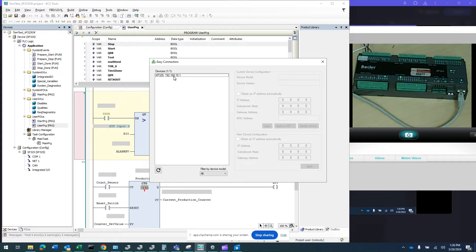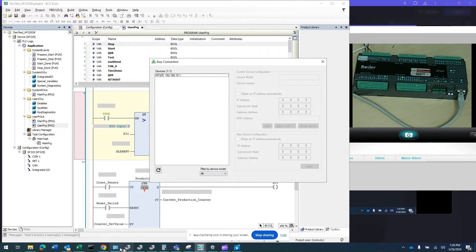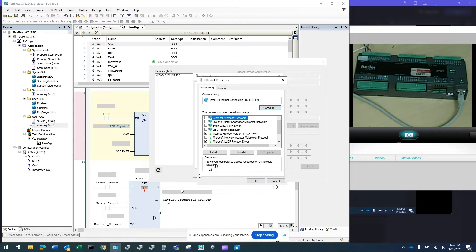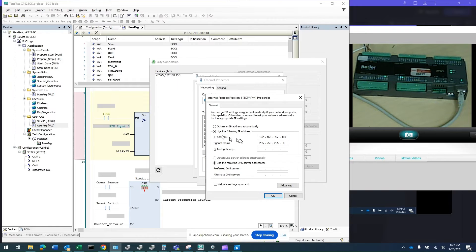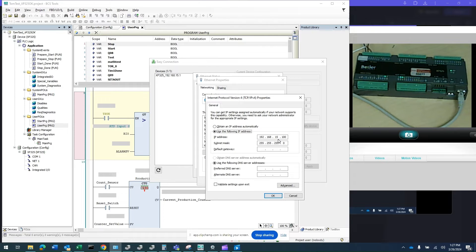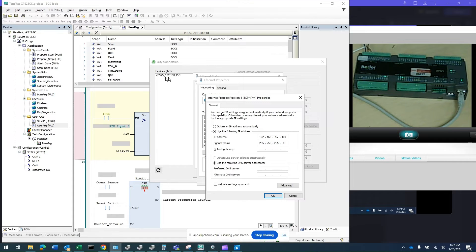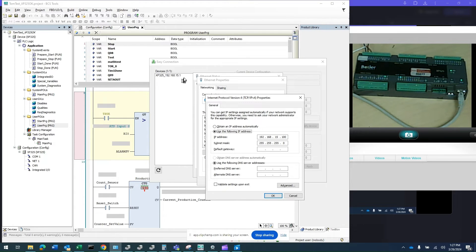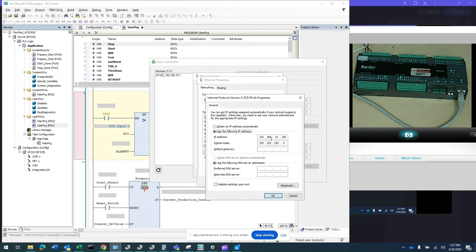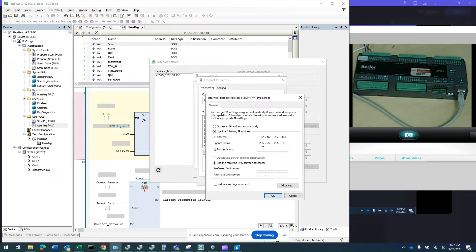At this point, go to your computer network adapter and select Internet Protocol version 4. Double click on that and make sure the first three octets are exactly the same. In this case, I set it to match 192.168.15. The last octet needs to be different than .1 because .1 is the PLC itself. I set mine to 192.168.15.100 with subnet mask 255.255.255.0.